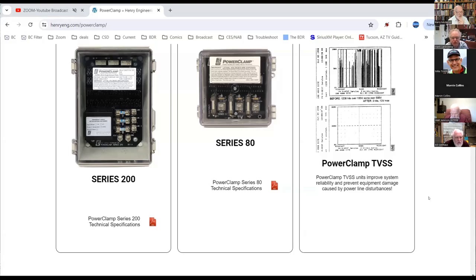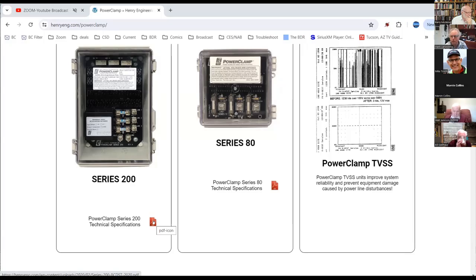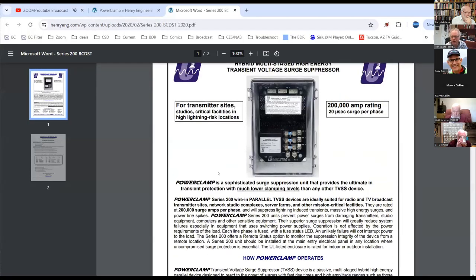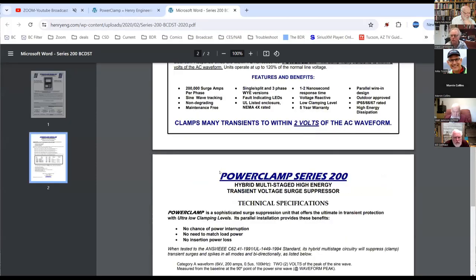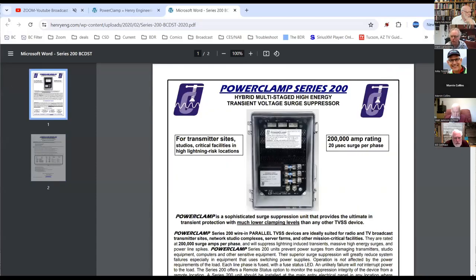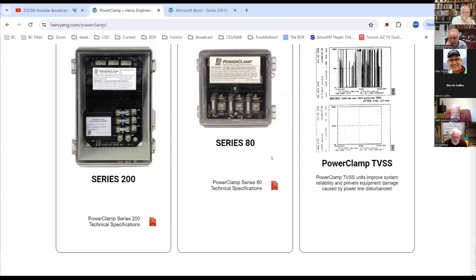So there you can see that the Series 200 is the bigger of the two, and then the Series 80 is the smaller one. Series 80 is fine for a downstream installation. Hopefully you have a bigger unit upstream. The best place to put these things is as close to the main panel as you can get them. Because as I said, these are operating in parallel with your incoming power service ground. So the lower the ground impedance, the more effective the unit is. So your main panel, that's generally where your neutral and ground wires are tied together, and that's where you have a direct connection to earth ground. So that's the best place to put it.